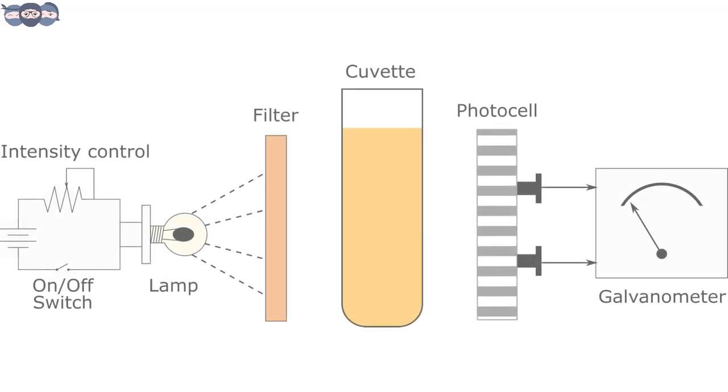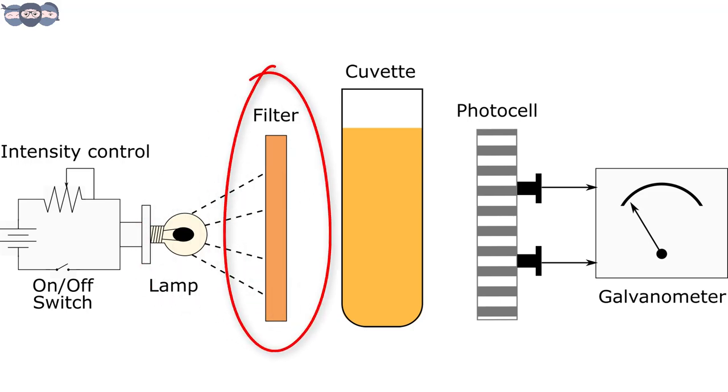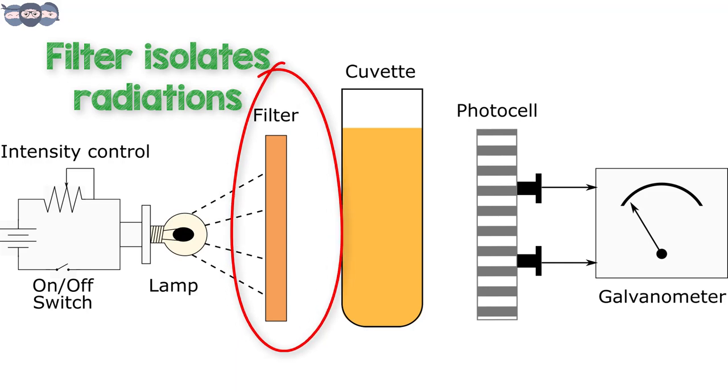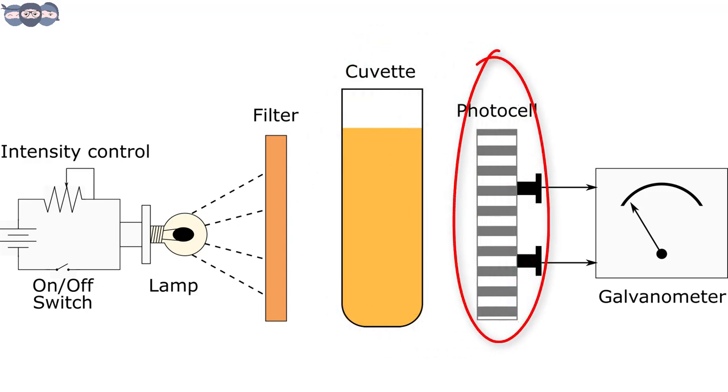As seen in the diagram, we can start with the construction of this instrument. The basic components of a single beam filter photometer are a light source, an absorption or an interference filter. It is called a photometer because the device that is used for isolating the wavelengths here is a filter. A cuvette is used as a sample holder and a photoemissive or a photovoltaic cell acts as a detector.